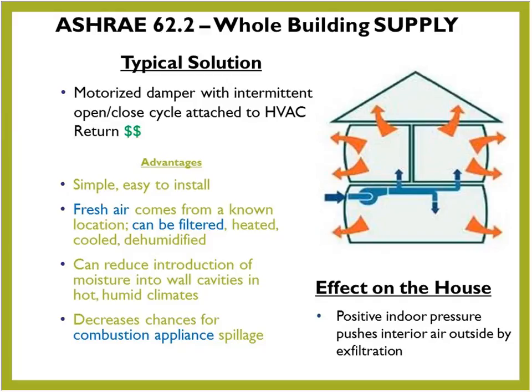With the exhaust-only approach, it does create a little negative pressure, not nearly as much as, say, a dryer or a kitchen range hood, but there is a little bit of negative pressure with the exhaust-only approach. So that's another benefit to the supply approach.